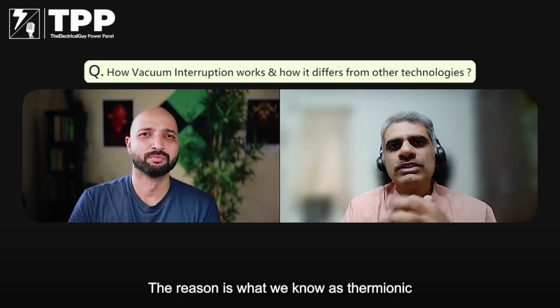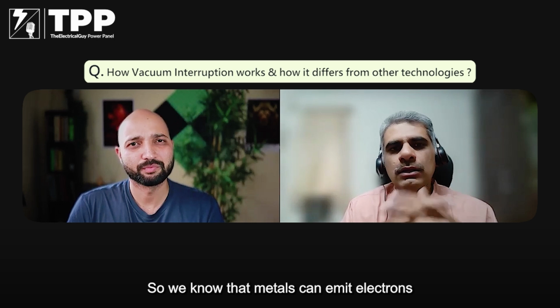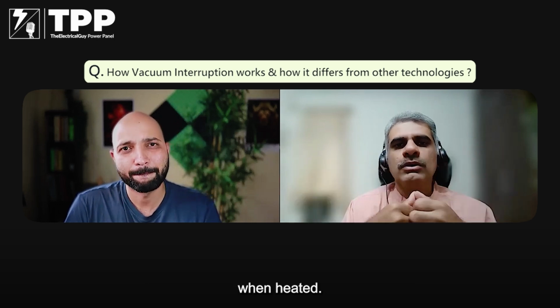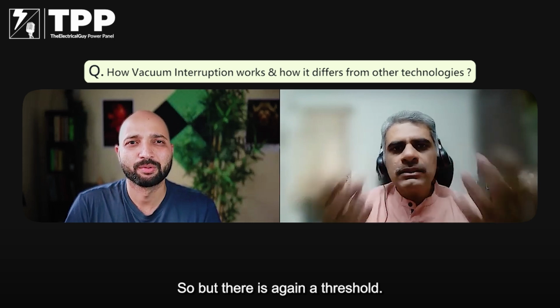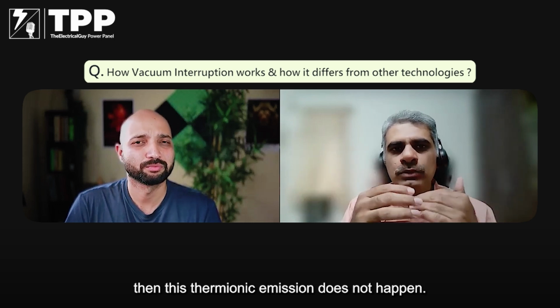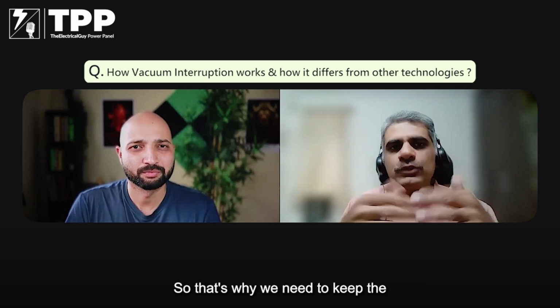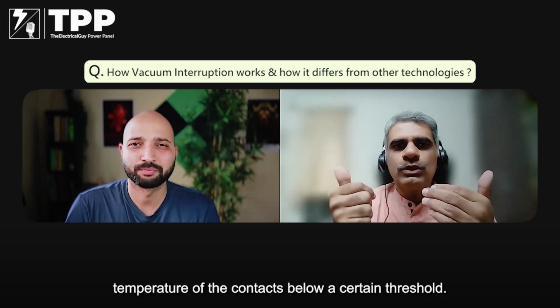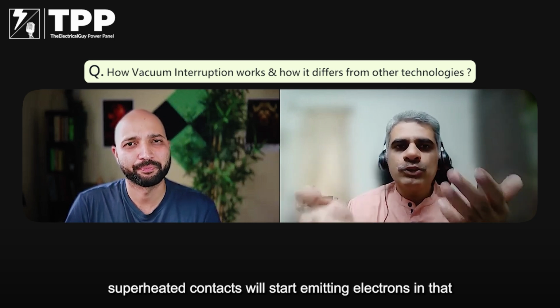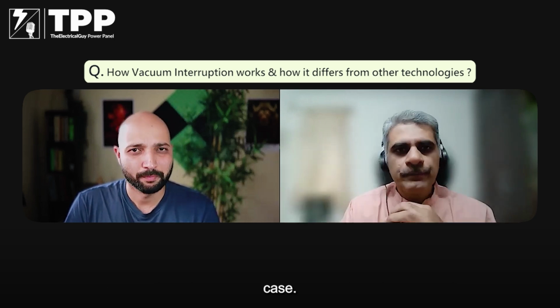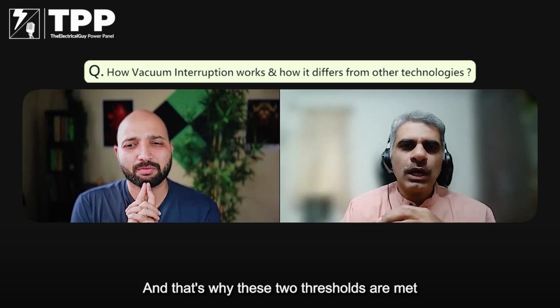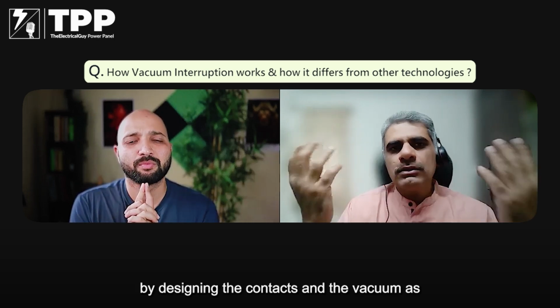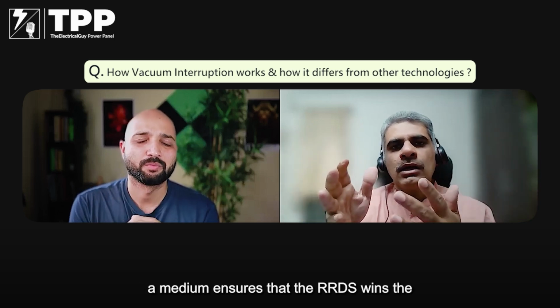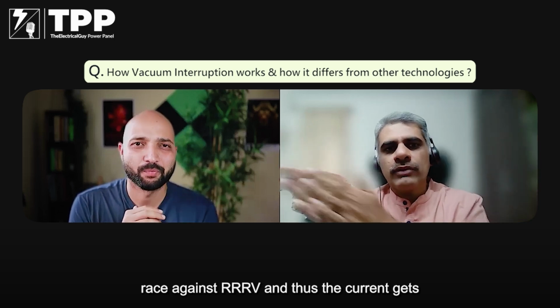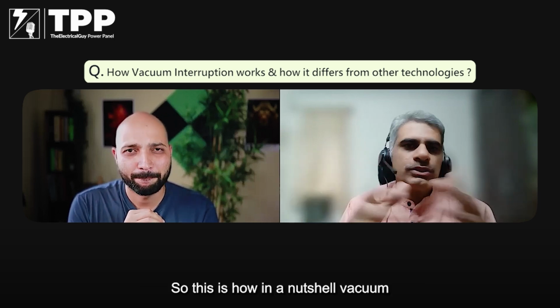The reason is what we know as thermionic emission. Metals can emit electrons when heated. But there is again a threshold. If the temperature is below a certain value, this thermionic emission does not happen. So that's why we need to keep the temperature of the contacts below a certain threshold. Otherwise, even if there's no metal vapor, the superheated contacts will start emitting electrons. And that's why these two thresholds are met by designing the contacts. And the vacuum as a medium ensures that the RRDS wins the race against RRRV, and the current gets interrupted. So this is how, in a nutshell, a vacuum interrupter works.